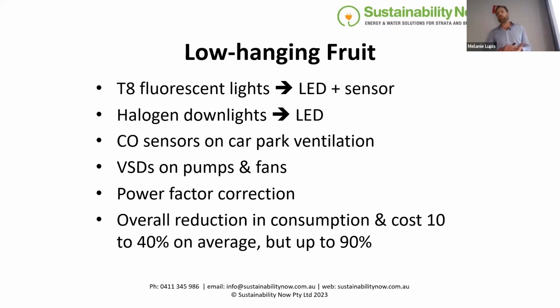So the question was, what causes bad power factor? It's inductive loads. So motors, and older motors that don't have capacitors built into them, and old fluoro lights with magnetic ballasts. We don't have the old fluoro lights with magnetic ballasts anymore, so that's why power factor is kind of a non-issue these days. It's pretty rare to see bad, unless it's some big old motors running in the place that don't have the capacitors built into them.